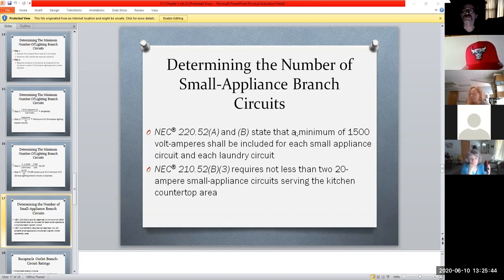So if we say that, okay, 1,500 VA, does that mean that's how many, and we know we can divide that out. We typically have 120 volts going through the house, so we can divide that 1,500 out by the 120 and figure out how many small appliance and laundry circuits we're going to actually be required to have, right? So in this case, the NEC states that you shall not have less than two 20 amp small appliance circuits serving a kitchen countertop area. So that means that you absolute at a bare minimum, even if it's a super tiny kitchen, are still going to be required to have two 20 amp dedicated breakers feeding the kitchen countertop area.